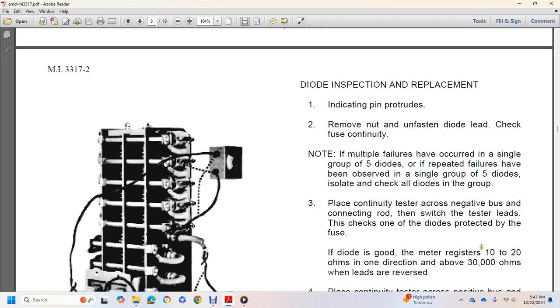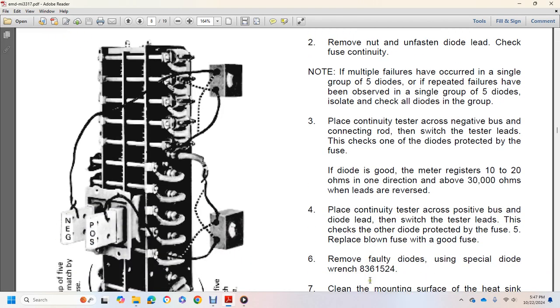If the diode is good, the meter registers 10 to 20 ohms in one direction and above 30,000 ohms when the leads are reversed. Place the continuity tester across the positive bus and the diode lead, and check the other diode protected with the fuse. 5. Replace the blown fuse with a good fuse.